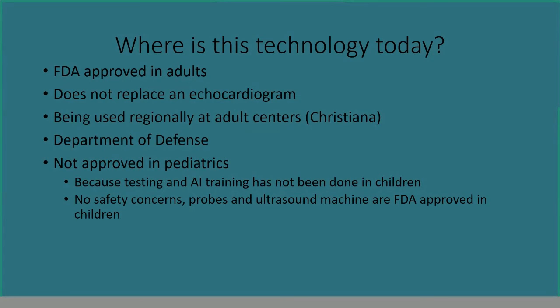So, in order to know whether the system can be used in children off the shelf, which would be ideal, because development of a new AI algorithm for the software would be a big project. It may need to be done, but we don't know that. So aim one was for us to determine the lower limit of patient size for this ultrasound system. What we were hypothesizing was that around 25 kilograms of body weight, where the current system, again, just off the shelf, the one that was optimized for adults, that's between 50 and 60 pounds, around 60 pounds, would stop generating diagnostic quality images.